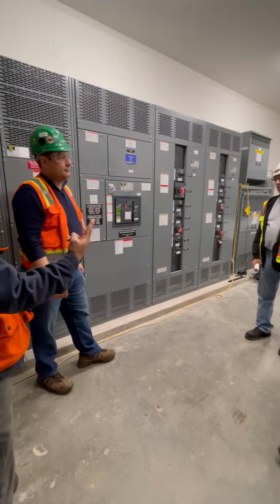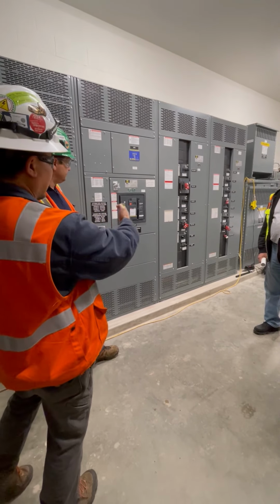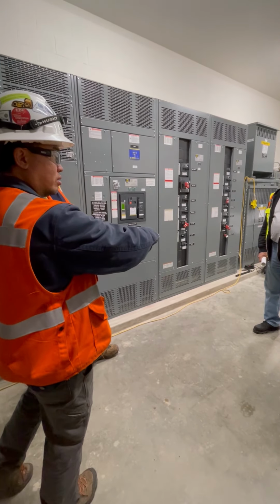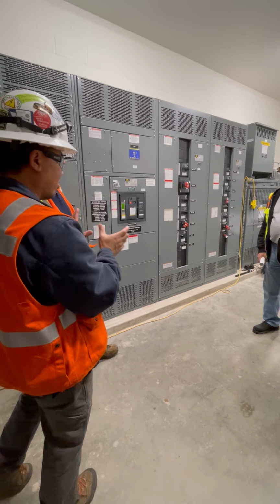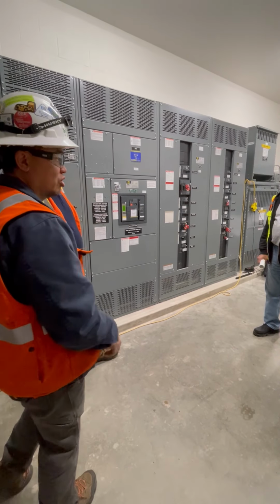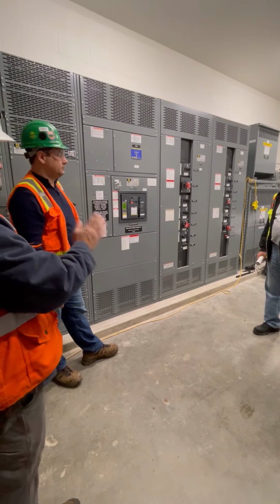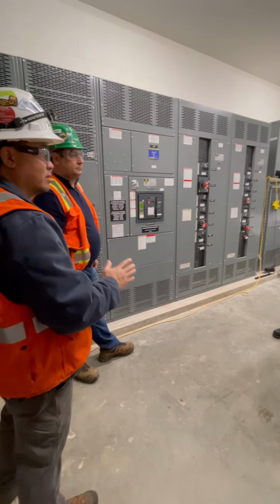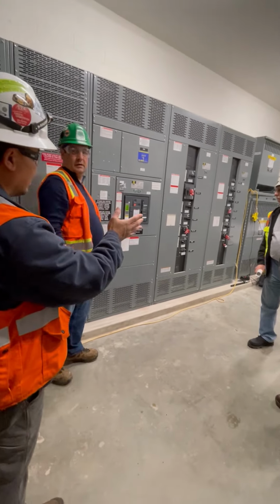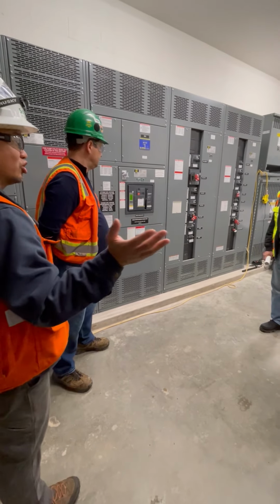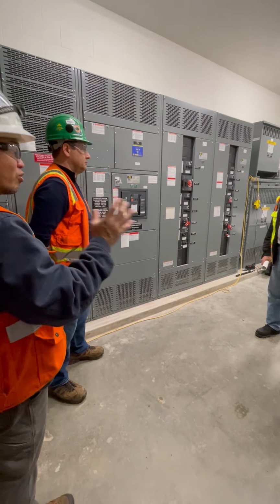Hospital requires 2 levels of ground fault, so your main and all the feeders in the switchboard. So they have 2 levels, so if there's a fault downstream, the feeder would trip, so you coordinate that. That's the NEC code requirement for hospitals. But it's not required for a school or anybody else, only for critical facilities.